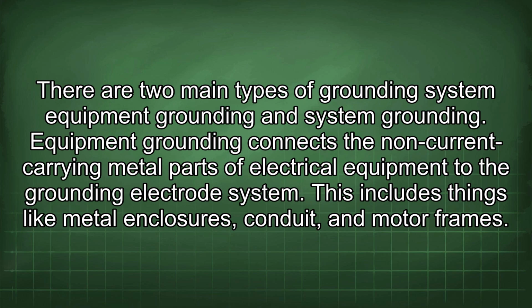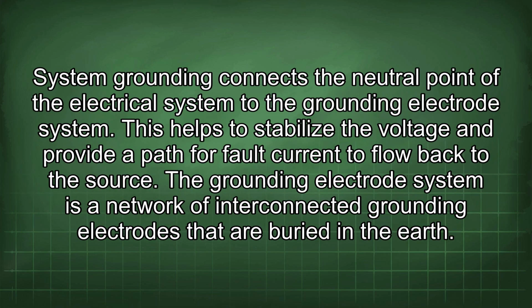There are two main types of grounding: equipment grounding and system grounding. Equipment grounding connects the non-current carrying metal parts of electrical equipment to the grounding electrode system. This includes things like metal enclosures, conduit, and motor frames. System grounding connects the neutral point of the electrical system to the grounding electrode system. This helps to stabilize the voltage and provide a path for fault current to flow back to the source.